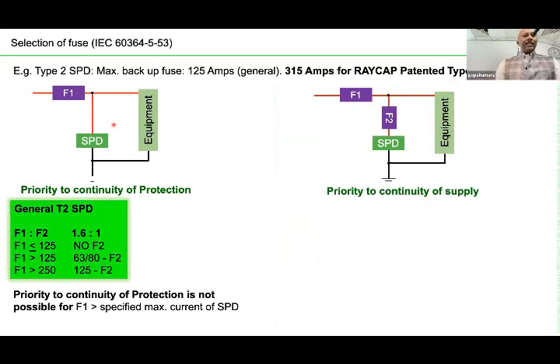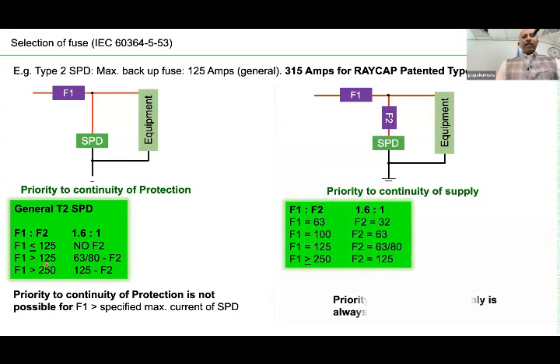one of the SPDs which we have shown here, say for example, in the first picture, you are deciding continuity of protection. That means you have not put any HRC fuse for the SPD. So F1 to F2 is 1.6 to 1. The HRC fuse for this particular SPD, let us say, is 125 amps. Now, if the rating of the F1 is more than 125 amps, then you definitely need an F2. So something like the second picture.